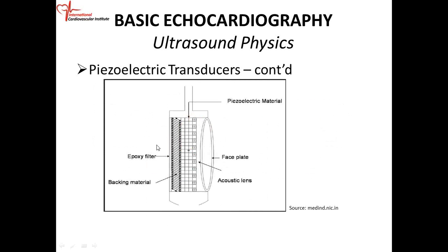Remember, you have the lens, and we said that you have to be careful that you don't destroy the lens of the transducer. So the first layer, you have this epoxy filter on the outside, and you can feel that. Just above that, you have what we call the backing material, and then just above the backing material is the piezoelectric material. Then you have the acoustic lens and the faceplate. Okay.